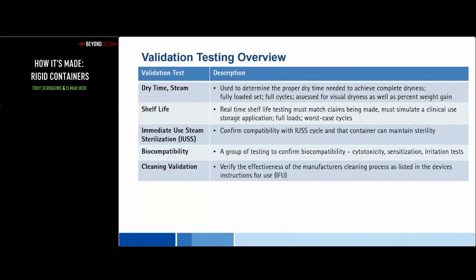In addition to these tests, there are just a few more. The next one is a pretty straightforward test. Of course, steam only is the dry time. It looks at what a standard dry time is. That's taking a fully loaded set and looking at how you achieve dryness. To achieve dryness, you have to show that it's visually dry and there's no increase in the percent of weight from moisture.